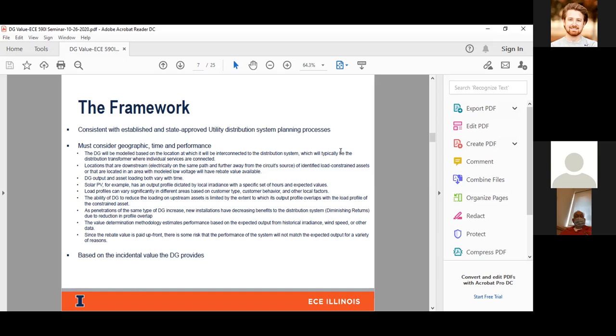Talking about time as a parameter here, as we all know, DG output and asset loading vary with time. Different loading profiles change based on the type of load, and they do vary with time. Similarly, the DG output varies with time. For solar, for example, there is a specific set of irradiance for the location where it's at, and also a specific number of hours that it's expected to operate. Typically, the ability of a DG asset to reduce loading on an upstream asset is when its generating profile overlaps with the load profile of the asset. So if you have a transformer that is being overloaded, and a solar asset with its output profile overlapping with that loading profile, that's when you see benefits and potential to reduce the loading.